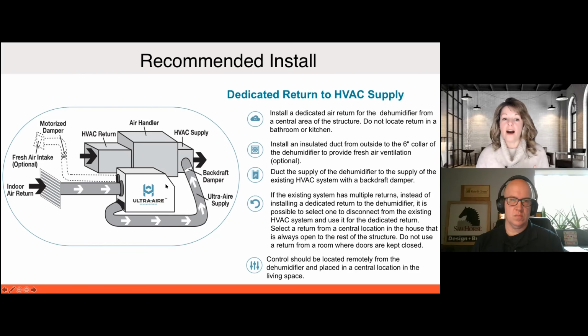So this is showing an air handler in an attic. You can absolutely do this if your HVAC system is located in a basement, larger mechanical closet, or smaller mechanical closet. We have smaller units. We have 8 units, all different sizes based on your application. And we can probably talk about sizing a little bit more later. But then we also have this optional fresh air. You don't have to use a dehumidifier to bring in fresh air. If you are using an ERV or a different ventilation strategy, you can just cap this off. You don't have to. But you absolutely can minimize purchasing and running other equipment by using the dehumidifier.